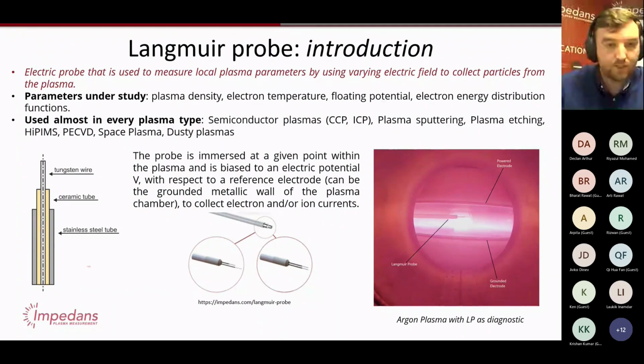So if we look here on the left side, you can see a zoom in of what the plasma measurement tip typically looks like. So you simply have a piece of wire, typically tungsten or something that can survive high temperatures. That's surrounded by some sort of insulating material. And then there's some other material which helps protect the probe from the plasma. And then these are all usually connected to a shaft, and that shaft will go out to some sort of vacuum port. In a few more slides, we'll actually show you a more detailed view of how you construct a probe. But in essence, it's a controlled measurement tip that sticks somewhere in the plasma, and you take the measurement at that point.